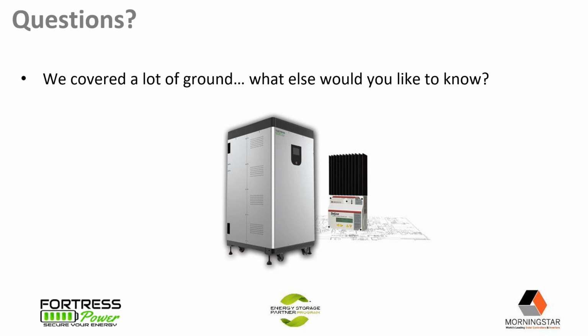To piggyback on what Brad said, typically, especially with batteries, you wouldn't want your battery to sit stagnant for more than 6 or 8 months. I always recommend that if you foresee the battery sitting somewhere longer than that, just cycle it one time during that period. Since electrolytes are a fluid, you want to make sure you're cycling it so the chemical reaction gives you the life cycles and lifespan we guarantee here at Fortress. Very good question about how long you can let it sit.